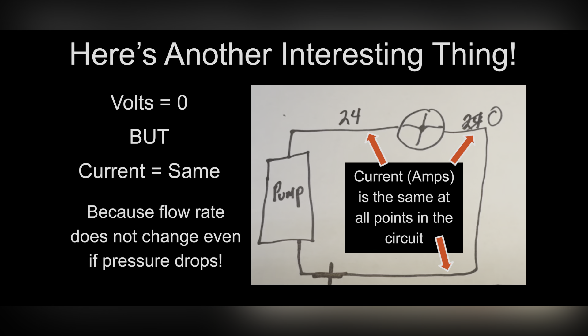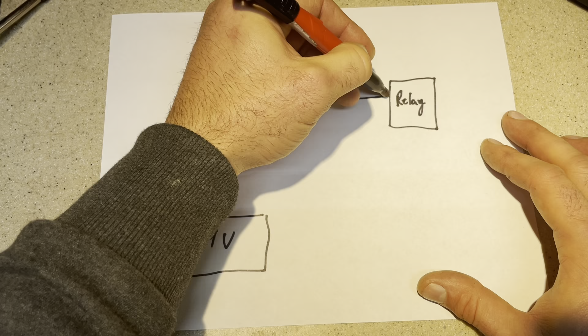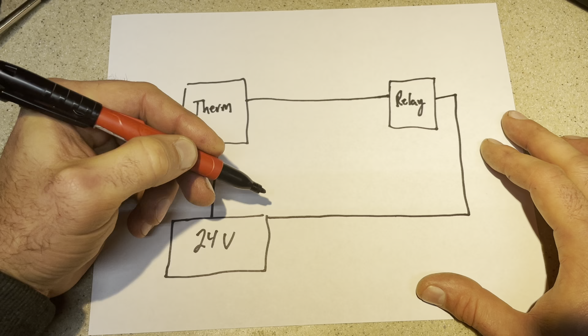I thought it would be cool to take what we learned in the analogy and apply it to a real troubleshooting scenario. So we have a thermostat here that's supplied with power from a 24 volt transformer. The thermostat goes out and powers a little relay, maybe for the blower or something. And then the relay has a connection back to the transformer through common.